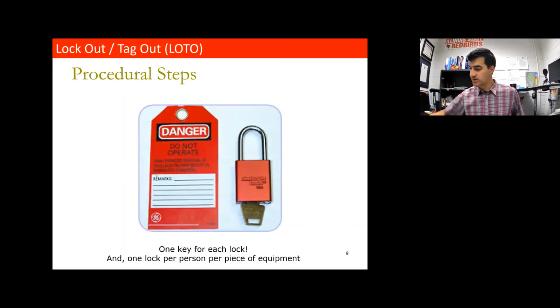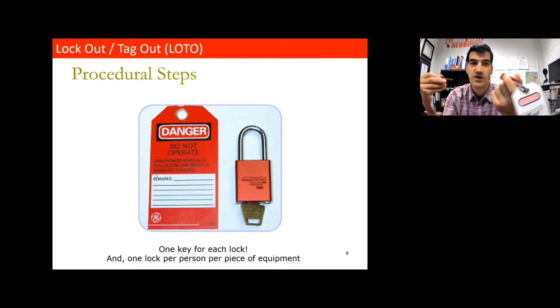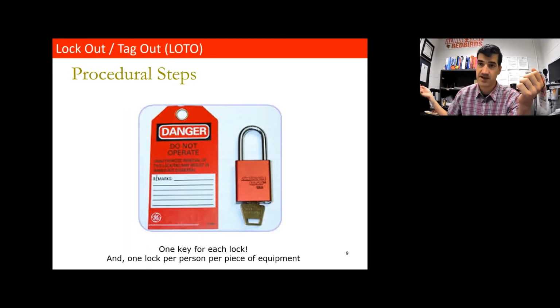This is important: each lock should have only one key. You don't want a situation where some other maintenance worker could have another key that works for this lock and could remove it. You want to make sure the person doing the maintenance is the only one with that key — one key for each lock.